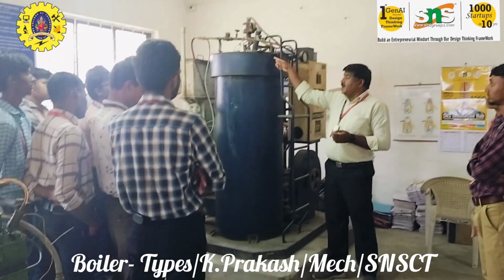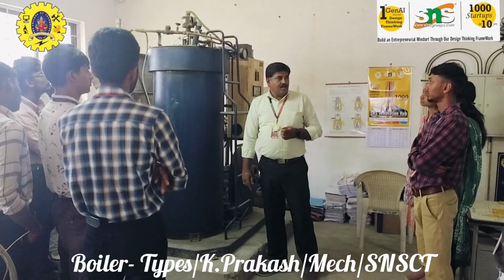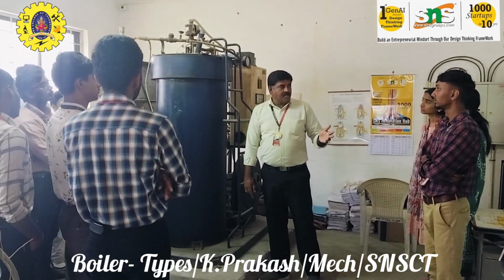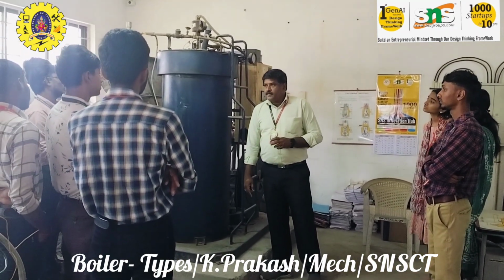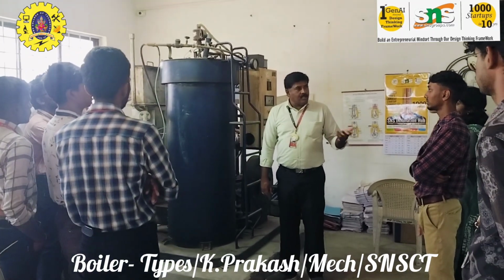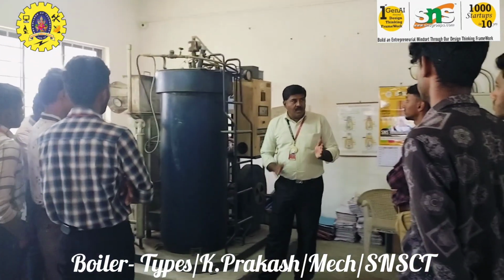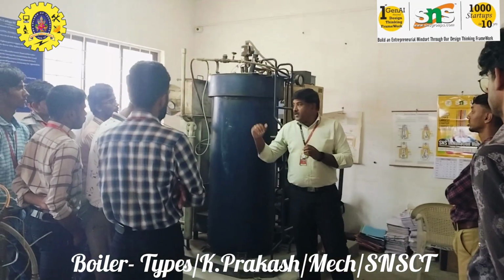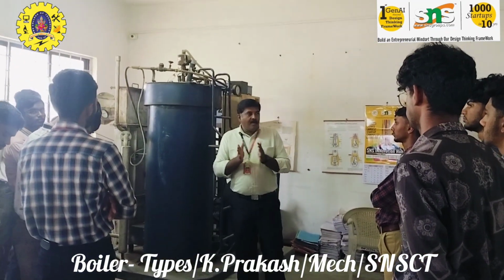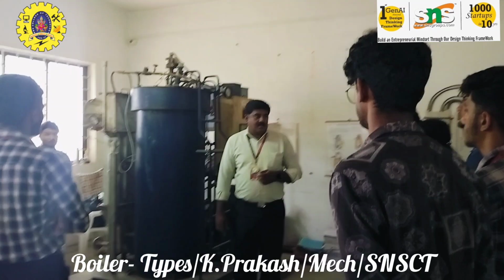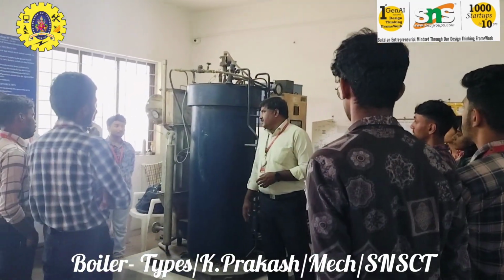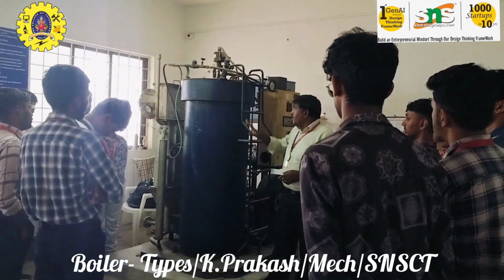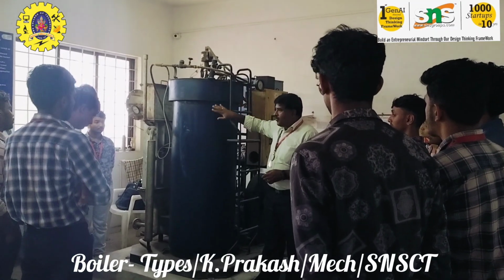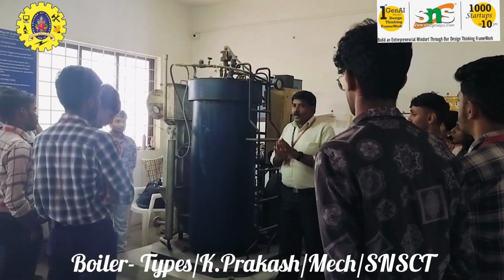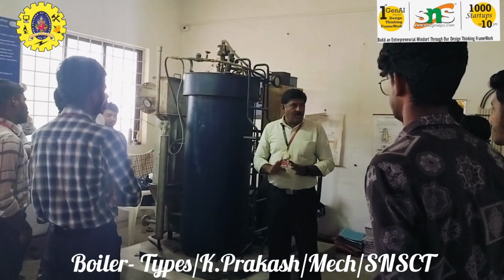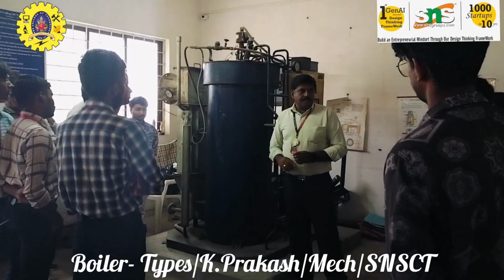So what will be the inlet temperature of the water when it is heated? Instead of 27 or 28 degrees Celsius, the temperature may be from 50 to 60 degrees Celsius. So we are increasing it by some 30 degrees Celsius using the waste heat which is going outside. That type of device is called an economizer. That is called an accessory. Mounting is very important for the working of a boiler, but an accessory is not essential. Accessories are required to increase the efficiency.